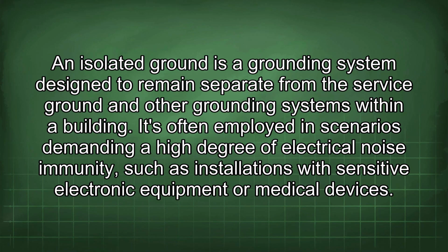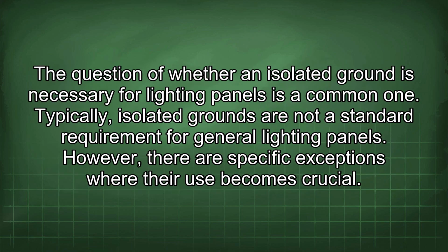An isolated ground is a grounding system designed to remain separate from the service ground and other grounding systems within a building. It's often employed in scenarios demanding a high degree of electrical noise immunity, such as installations with sensitive electronic equipment or medical devices. The question of whether an isolated ground is necessary for lighting panels is a common one. Typically, isolated grounds are not a standard requirement for general lighting panels. However, there are specific exceptions where their use becomes crucial.